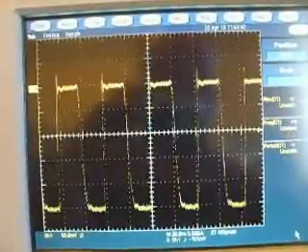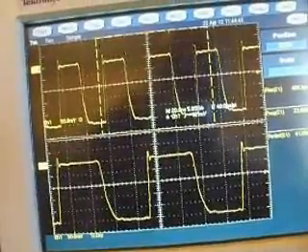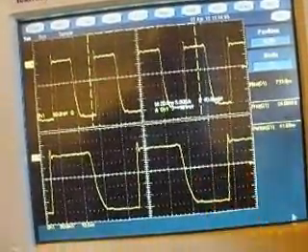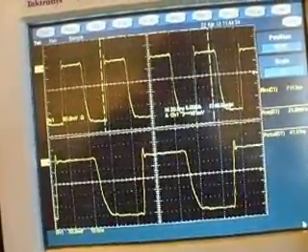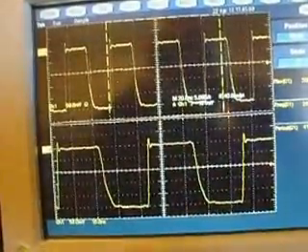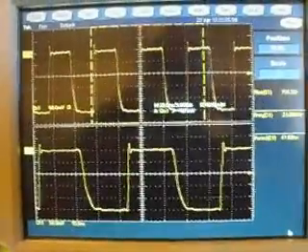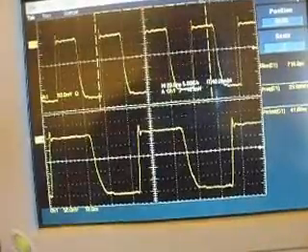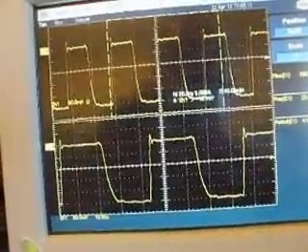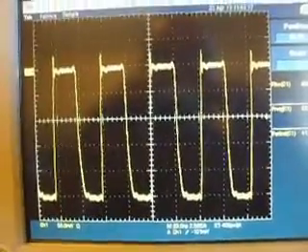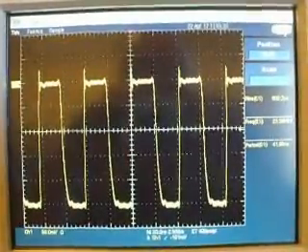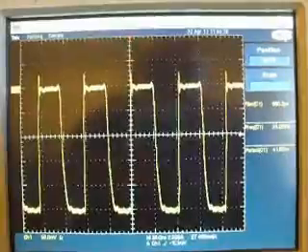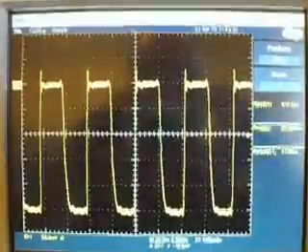And we could probably, if we were to zoom, I'm not sure. I'm in just as close or maybe I'm not. You could use the zoom tool to be able to look at the signal just as close as you were before but still be getting your frequency measurements and so forth. I just haven't played with the scope enough to be quick at doing it. Probably if we do fast acquisition, it just goes to the regular screen. And this has been called, fast acquisition's been called different things on different scopes. It's been referred to as digital phosphor, InstaView was another one. Just marketing terms more than anything else.